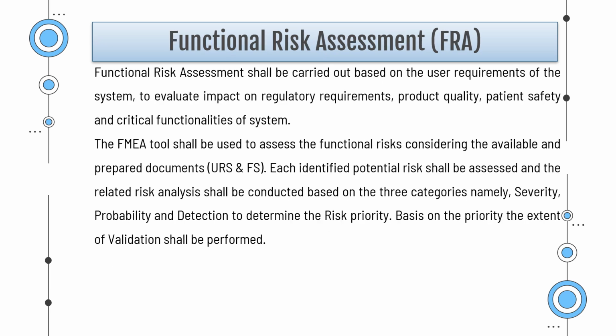Functional risk assessment shall be carried out based on the user requirements of the system to evaluate impact on regulatory requirements, product quality, patient safety and critical functionalities of the system. The FMEA tool shall be used to assess the functional risks, considering the available and prepared documents, URS and FS. Each identified potential risk shall be assessed and the related risk analysis shall be conducted based on three categories, namely severity, probability and detection, to determine the risk priority. Based on the priority, the extent of validation shall be performed.